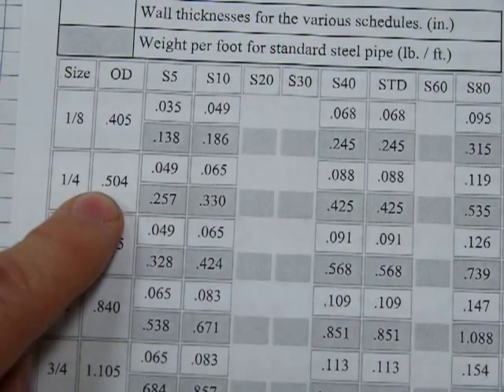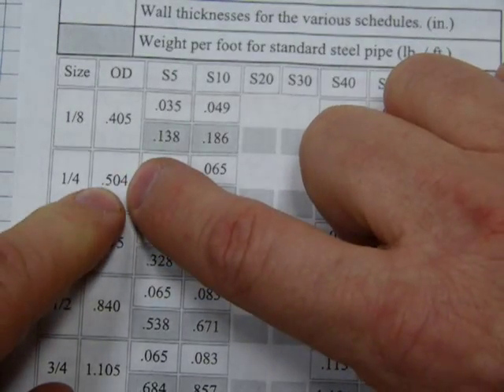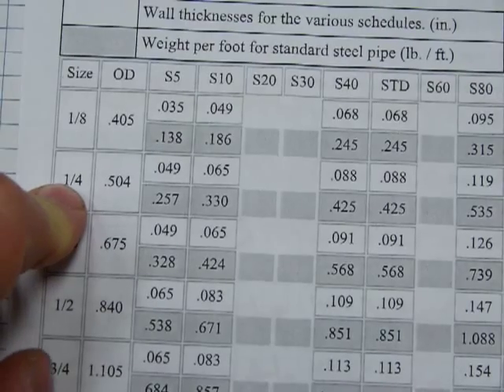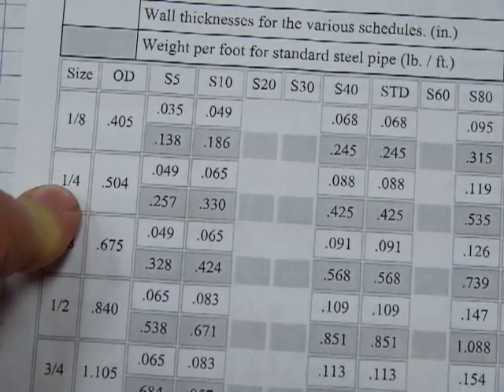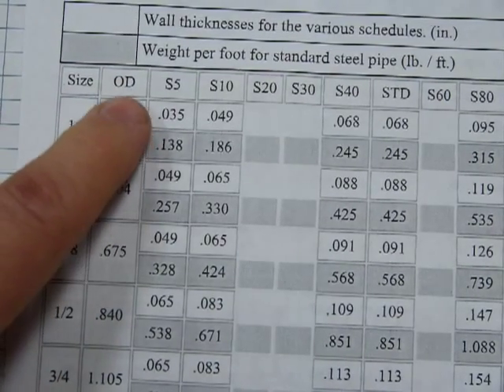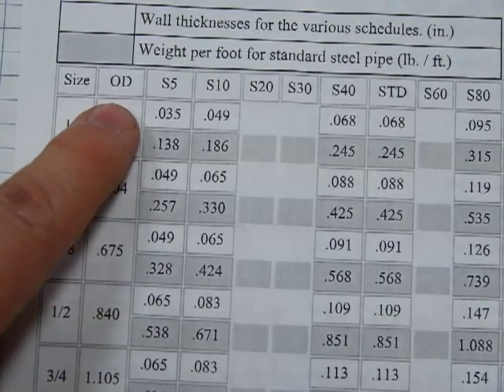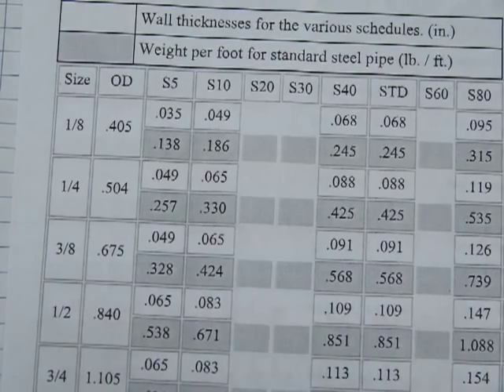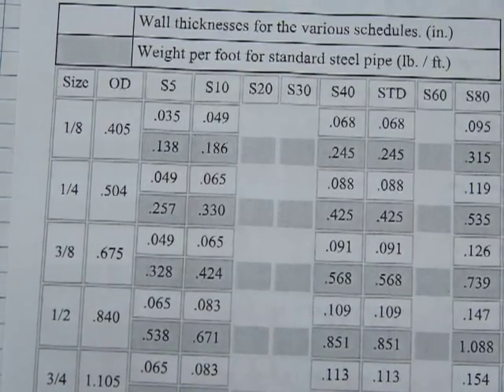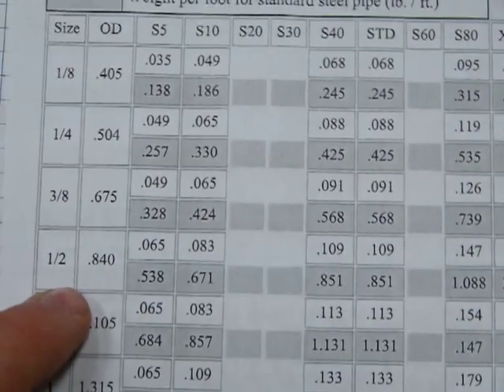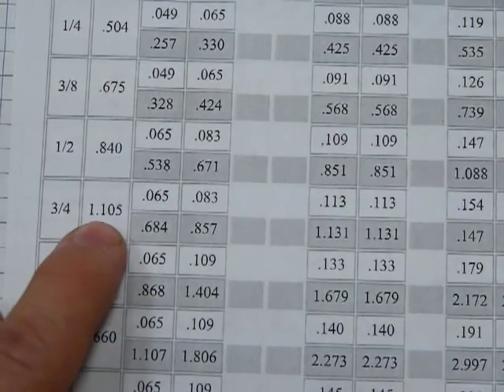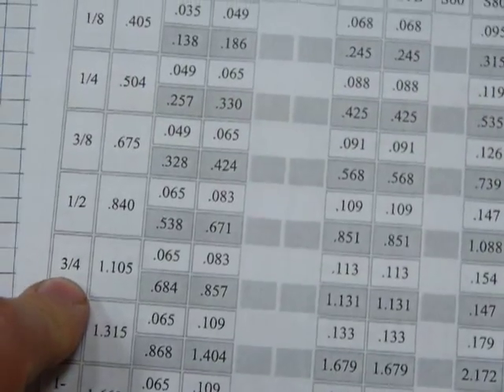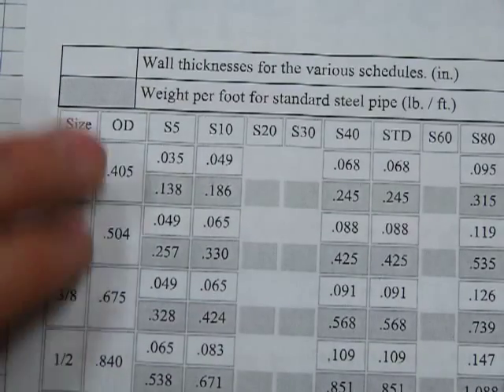For example, this 0.504 inches — we'll round it down to 0.5 inches, which is half an inch — yet this is a quarter-inch pipe. Don't worry about it; you don't need a history lesson on why it is so, just deal with it. The nominal size of the pipe doesn't really correspond but somewhat relates to the actual size. The amounts shown are the actual sizes of the pipes, and in any pipe schedule you look at the numbers will all be decimal inches. For example, 1.1 inches is a little over an inch — say an inch and a sixteenth — yet that pipe's nominal size is three-quarter inch. That's how the first two columns work.